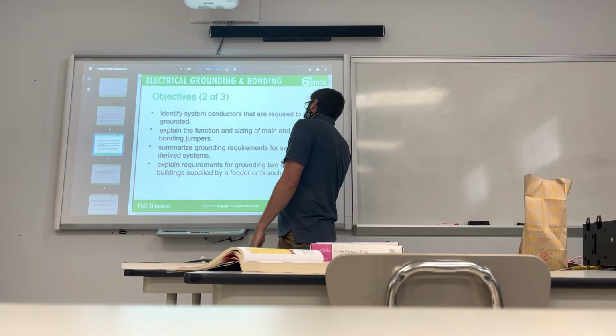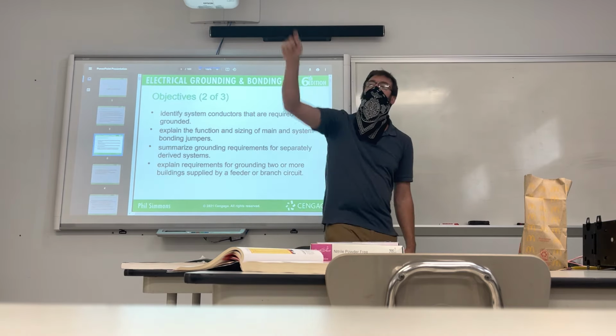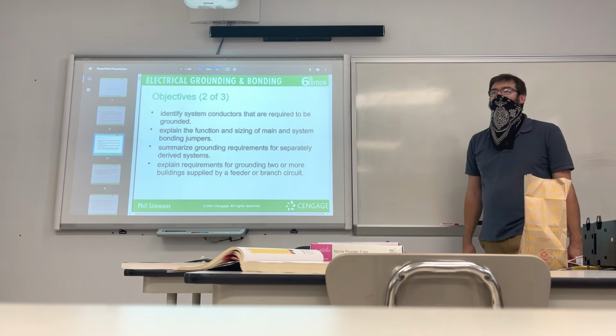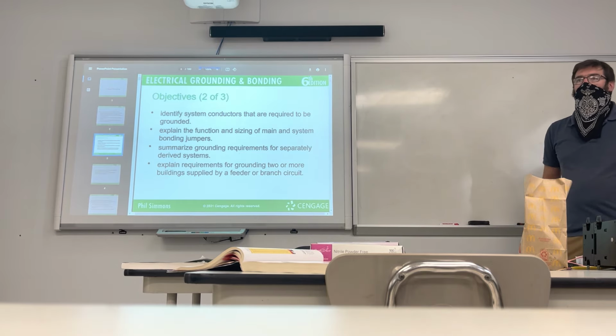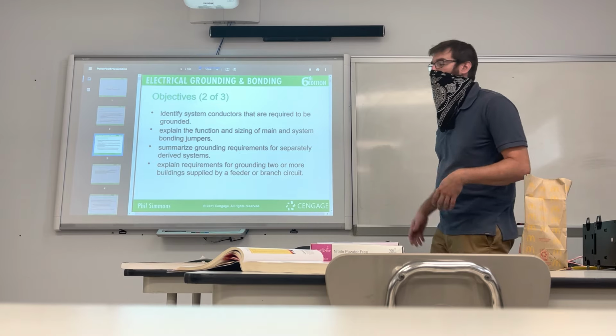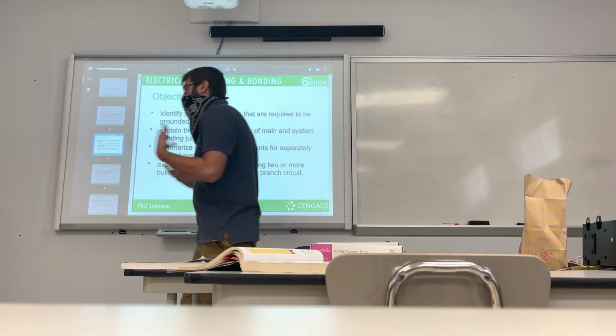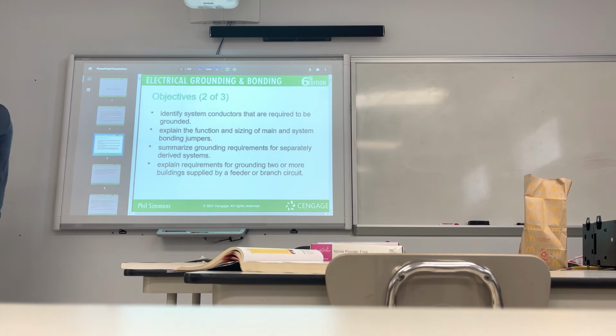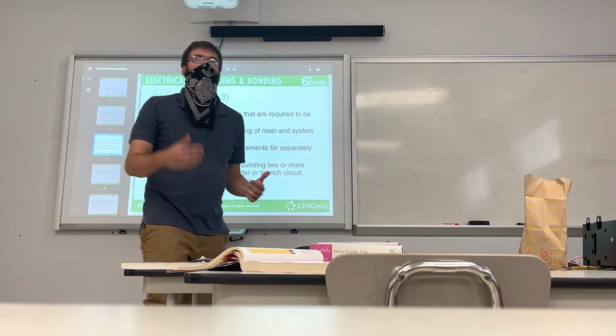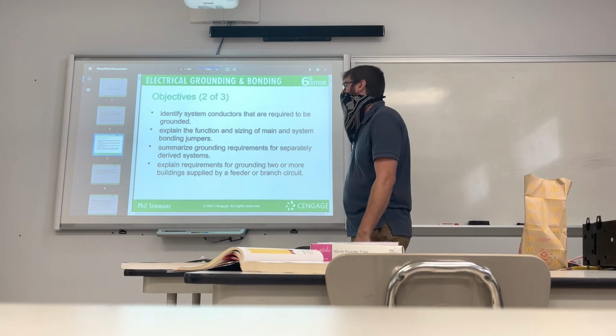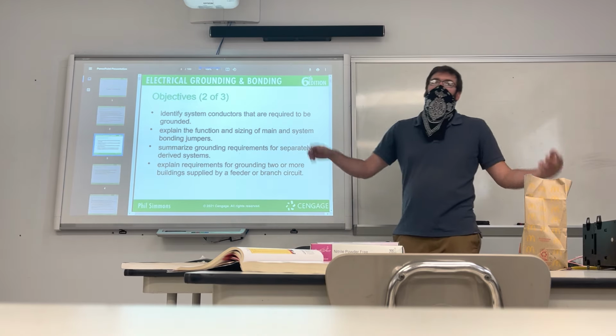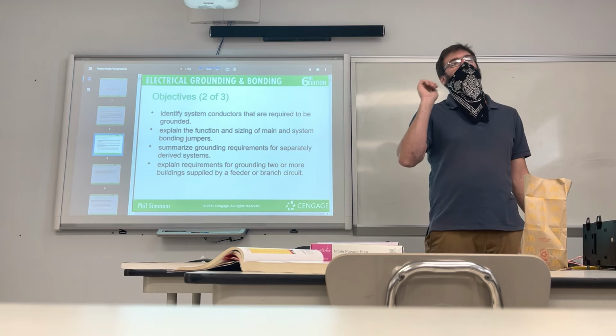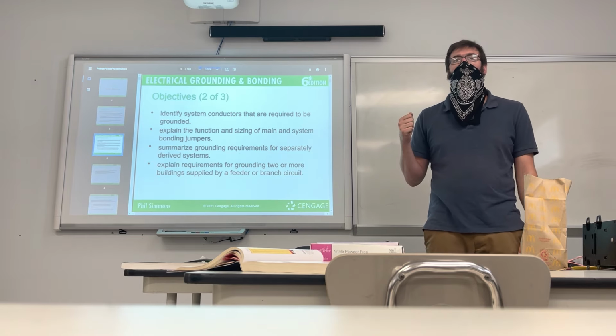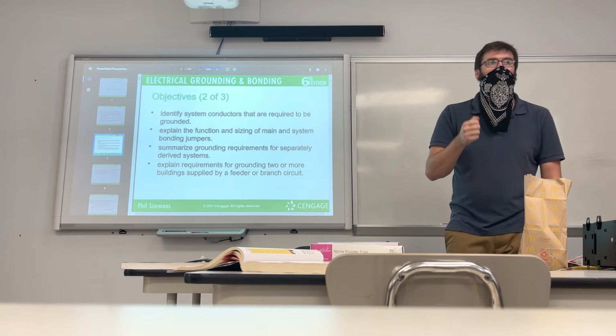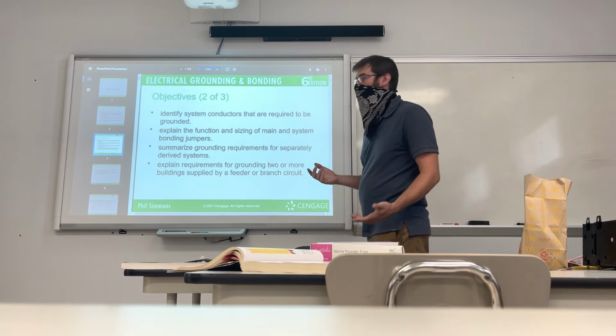All right, summarize the grounding requirements for separately derived systems. What's an example of a separately derived system? Power coming into your house is not considered separately derived. That's the service. That's from the street. What's a separately derived system? What's an example? A generator. Generator. Give me another example. Battery box. Battery box, right? Any different source of power other than the street, okay? And you usually have to ground those as if they're coming from the street. So the ground or the neutral coming off of that usually has to be grounded right there. And then continue into your house and then grounded again. Same thing with the battery box, okay?